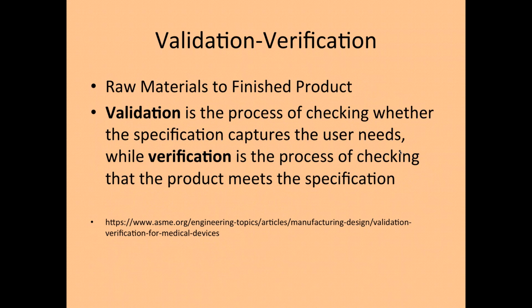Validation and verification, you're going to be introduced to these if you haven't already. To validate your process is checking whether the specification captures the user needs, and verification is the process of checking that the product meets the specification. So I put a little link at the bottom here on verification for medical type devices. So if your validation says that I meet my user needs and I verify that the product meets the specification, you've met the standard for this.